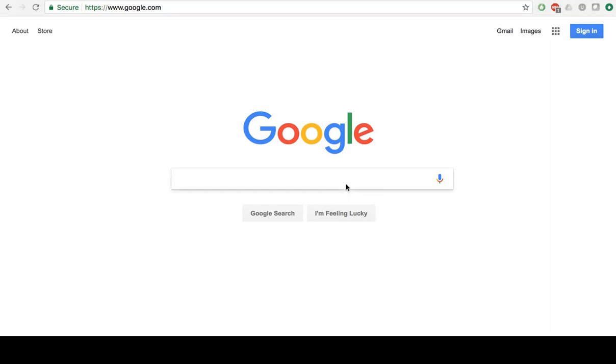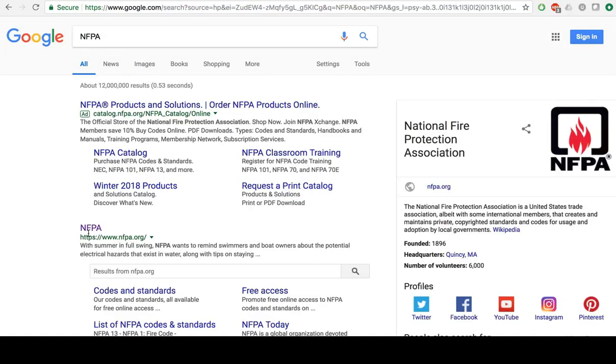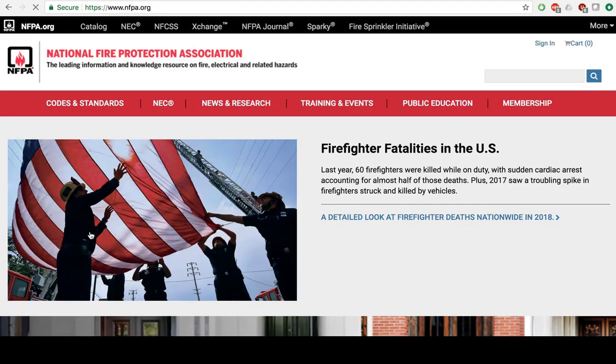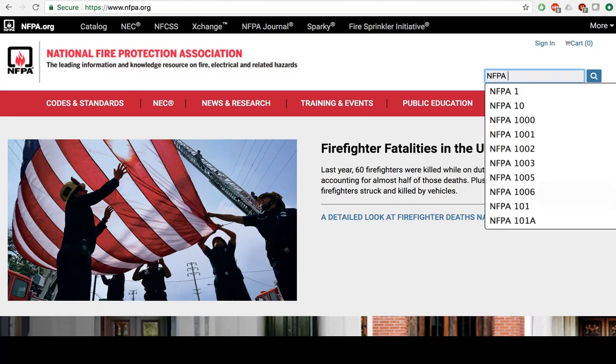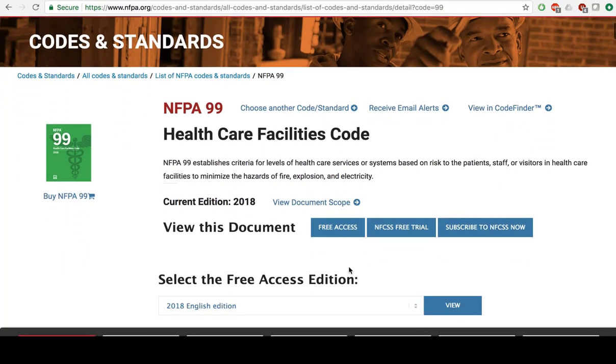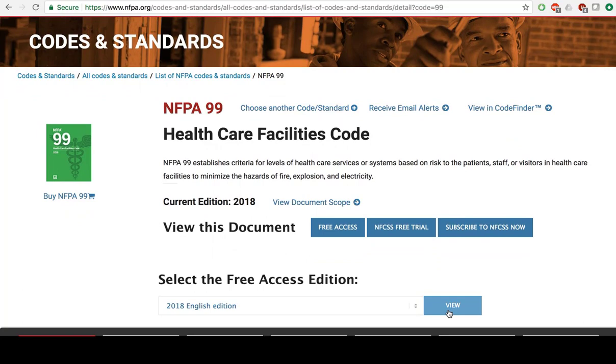The first step is to go to the NFPA website. As biomedical equipment technicians and healthcare technology professionals, the codes and standards we are interested in are the NFPA 99 healthcare facility codes. Here we can access these codes. Click on the free access, select the most recent edition, and hit view.